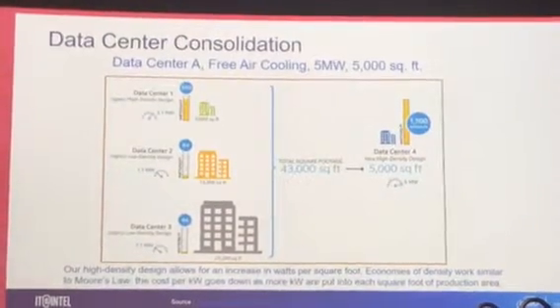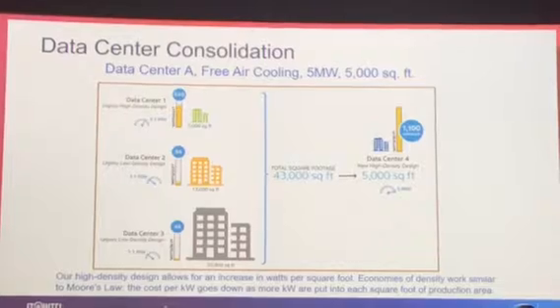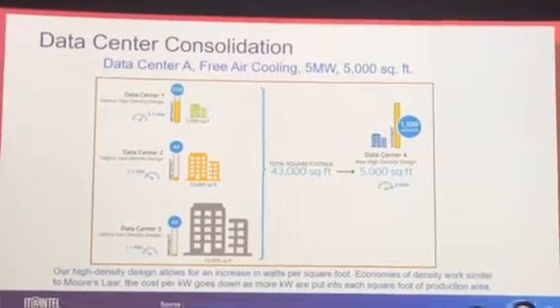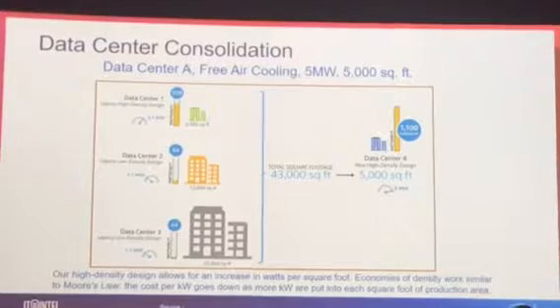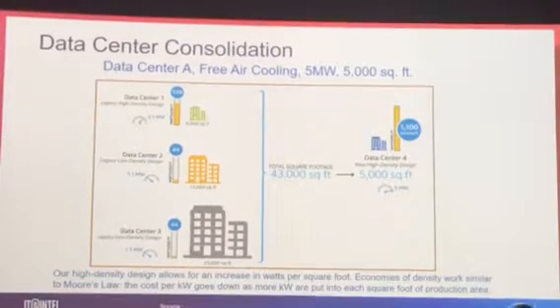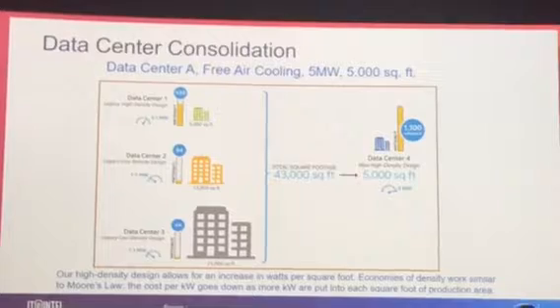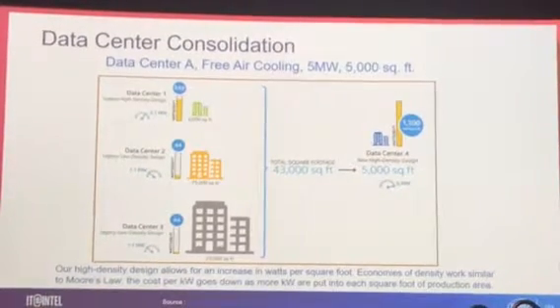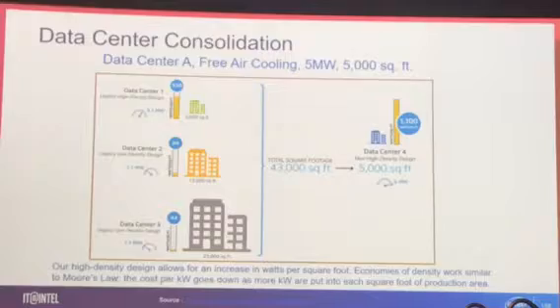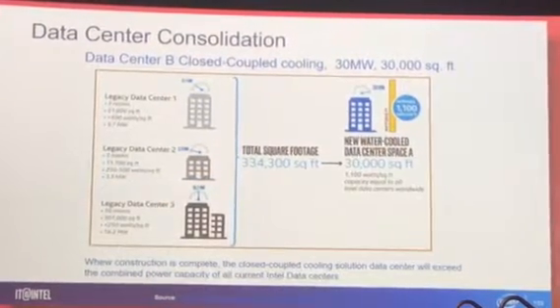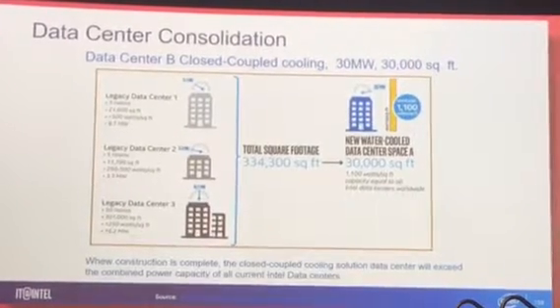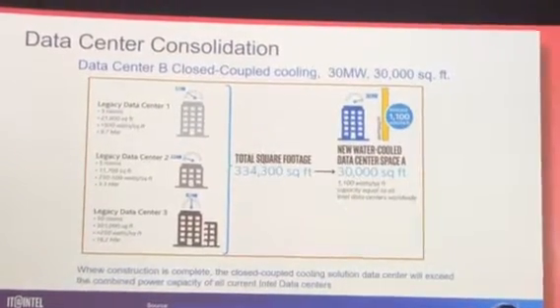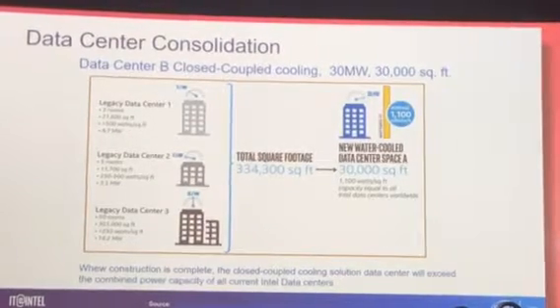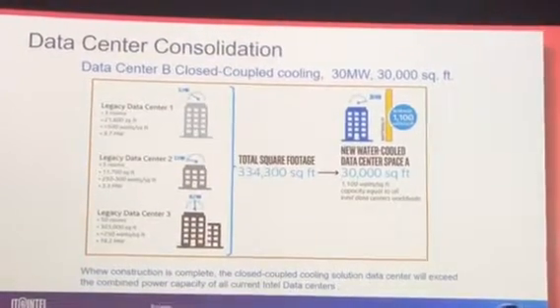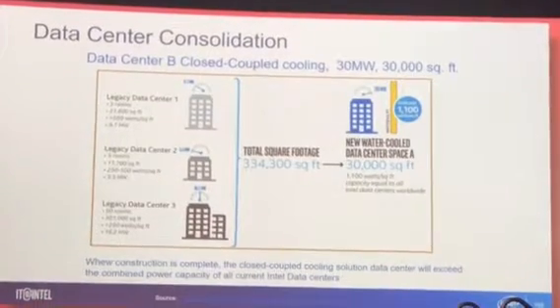And just to give you some idea, the 5 megawatt data center, we took 3 other data centers in Intel, which required 43,000 square foot, and we were able to take those 3 and put them in one data center, 5,000 square foot. So you can see the density, it's 1,000 watt per square foot, really high. Same for the other one. We have 3 other data centers, total of about 30 megawatt, which takes 334,000 square foot, and we were able to squeeze them into one 30,000 square foot area.